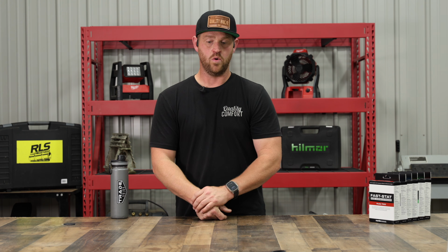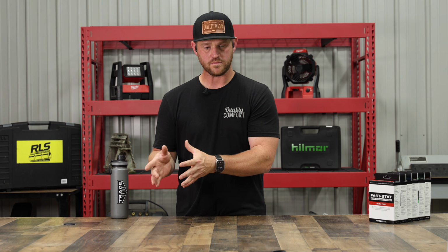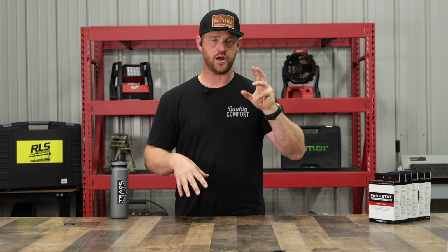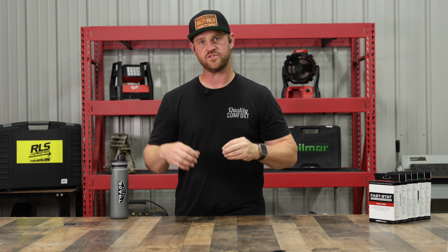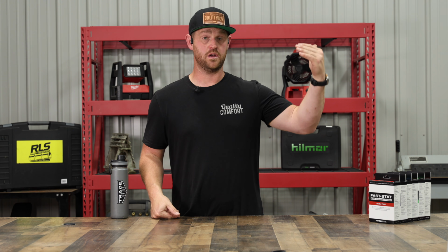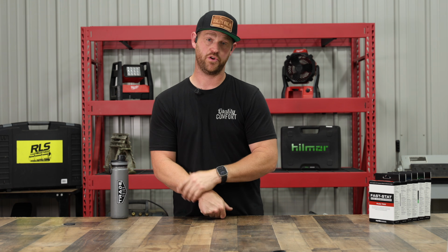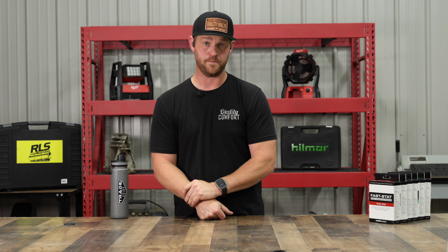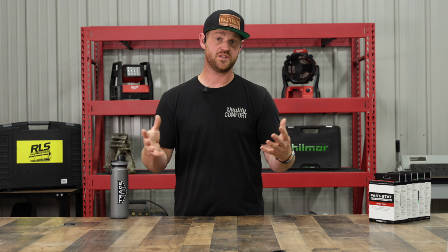Where the inverter-based equipment shines, because it can tailor its capacity, it can shut fans off, turn them on, and just do different things, it can actually operate, like some manufacturers can operate down to a negative 22 degree outdoor ambient temperature. So that means, depending on your climate, now obviously every region is different, but in Tennessee, we do get cold weather.